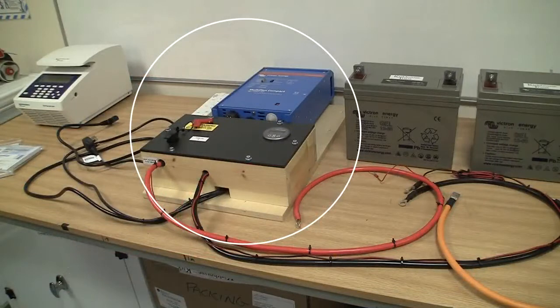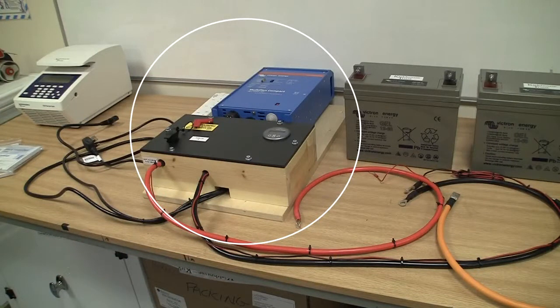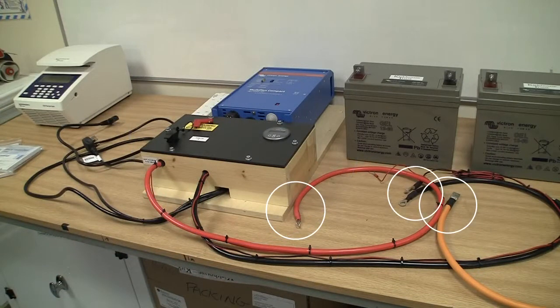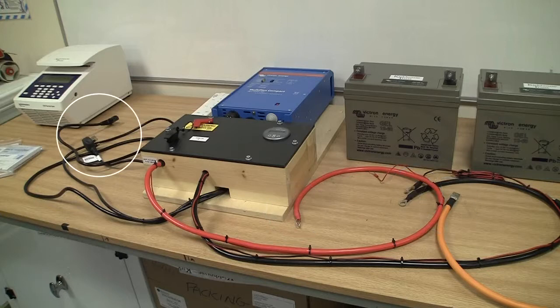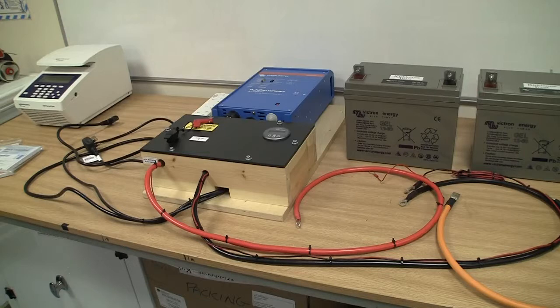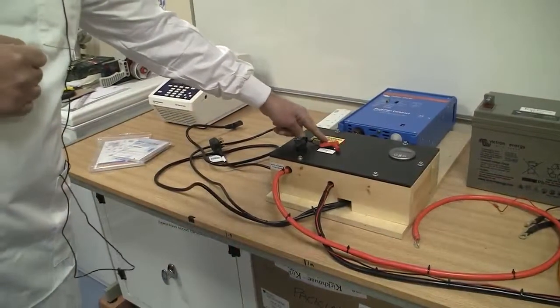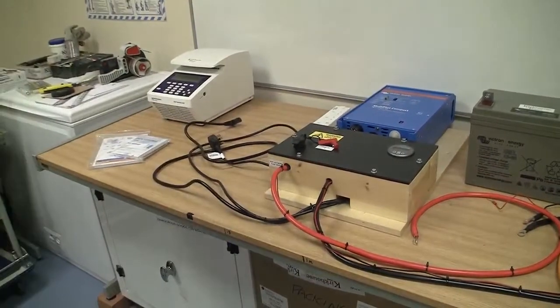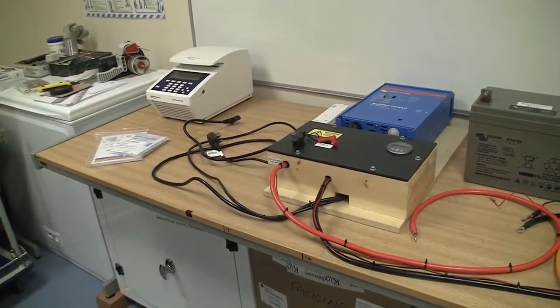You then have the inverter battery backup and the various wires that are leading from it. The positive, the negative with the monitoring wires and further over you see the power in and power out leads. The thing to check at this point is that the red key is out and loose and this way it's safer to make all the connections.